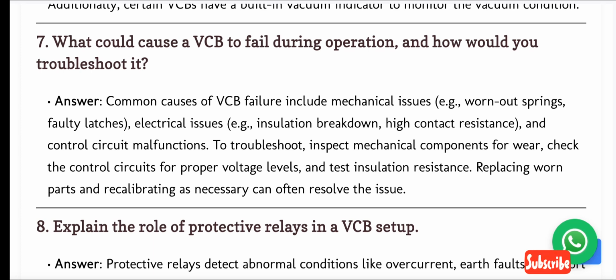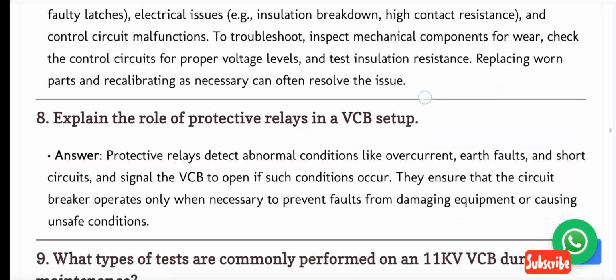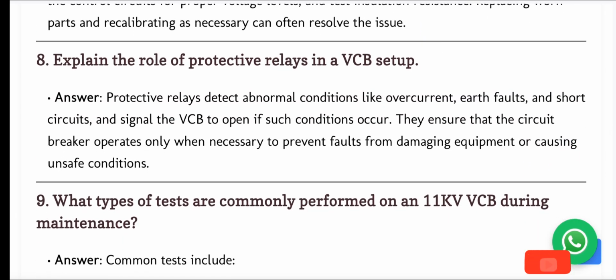Answer. Common causes of VCB failure include mechanical issues, e.g., worn-out springs, faulty latches, electrical issues, e.g., insulation breakdown, high contact resistance, and control circuit malfunctions. To troubleshoot, inspect mechanical components for wear, check the control circuits for proper voltage levels, and test insulation resistance. Replacing worn parts and recalibrating as necessary can often resolve the issue. 8. Explain the role of protective relays in a VCB setup.